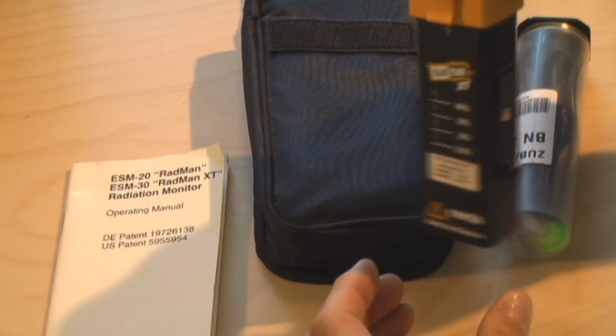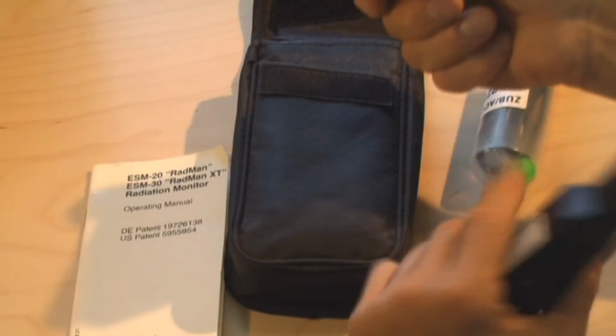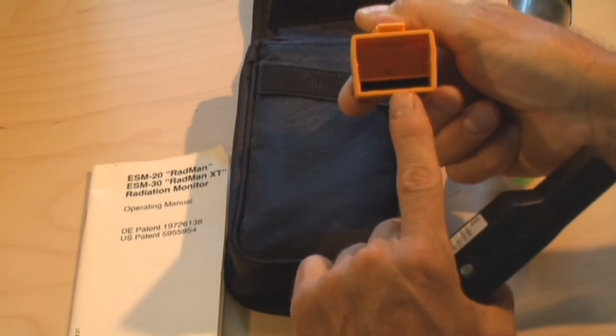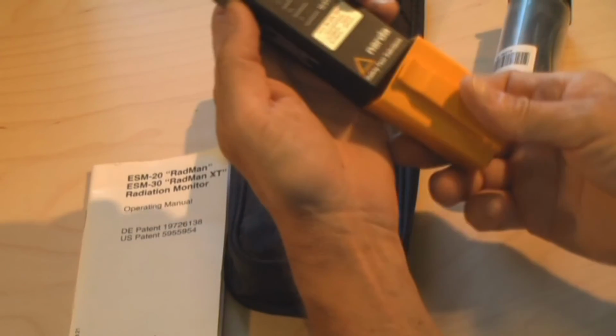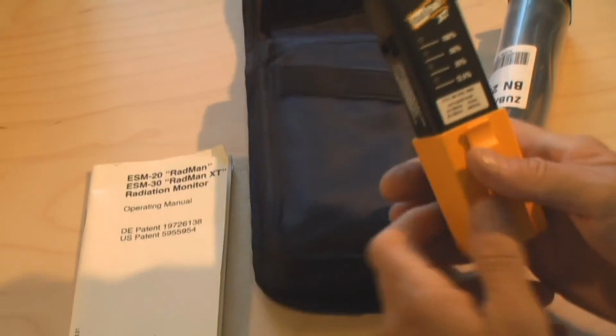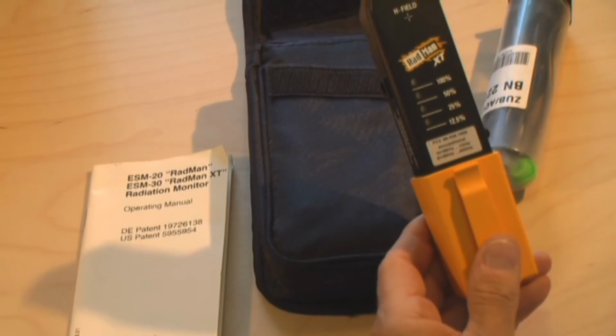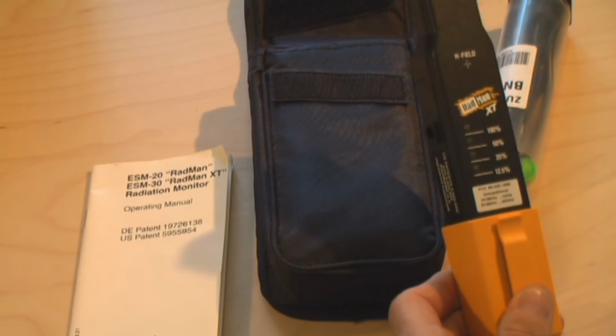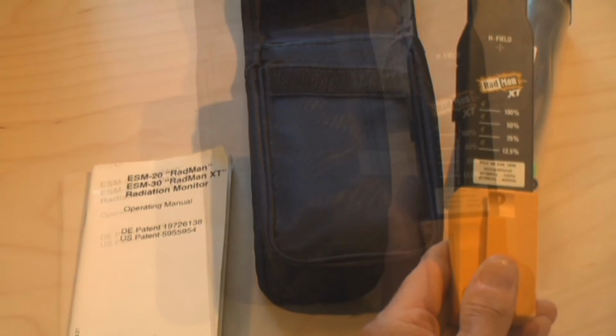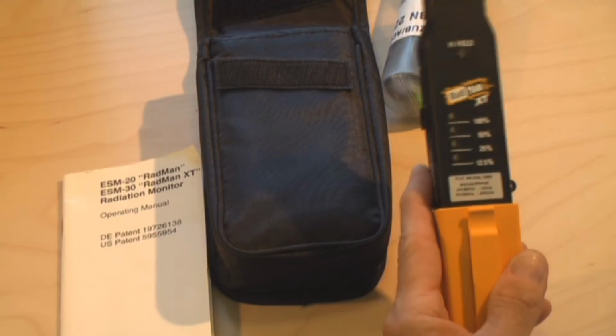As a personal monitor to be worn in a pocket, the yellow cap stays on to reduce interaction with the body. The second mode is using this monitor as a peak detector. You must remove the yellow cap with absorber material and typically place it on the bottom. You now have a fairly isotropic detector to use in a quasi-survey type function.